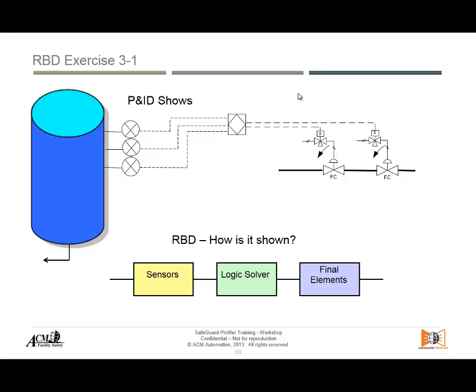What is the answer? For the three sensors, in reality we cannot tell whether it's one out of three or two out of three, so it is M out of three. For the logic solver it is one out of one. For the final elements we have the solenoid and the valve in series, so that combination will be two out of two.